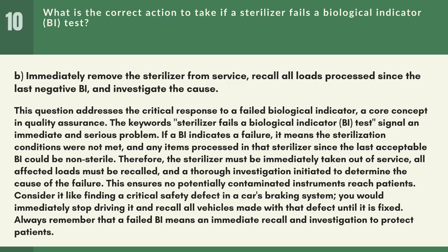Therefore, the sterilizer must be immediately taken out of service, all affected loads must be recalled, and a thorough investigation initiated to determine the cause of the failure. This ensures no potentially contaminated instruments reach patients. Consider it like finding a critical safety defect in a car's braking system. You would immediately stop driving it and recall all vehicles made with that defect until it is fixed. Always remember that a failed BI means an immediate recall and investigation to protect patients.